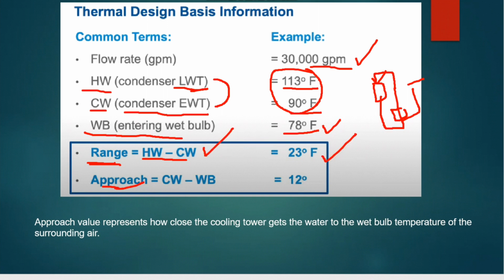Coming to the approach, it is CW minus wet bulb. In these two cases, the entering water temperature minus the entering wet bulb temperature gives you the answer of 12 degrees. This is the approach. The approach value tells you how close the cooling tower gets the water to the wet bulb temperature of the surrounding air.